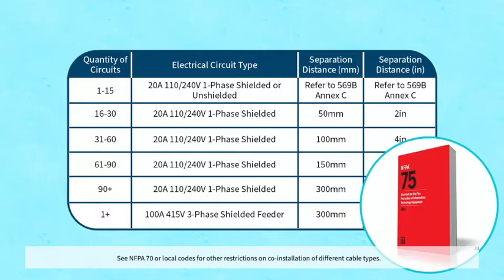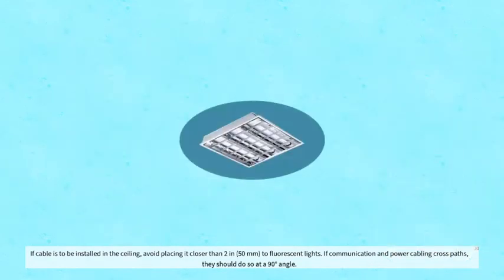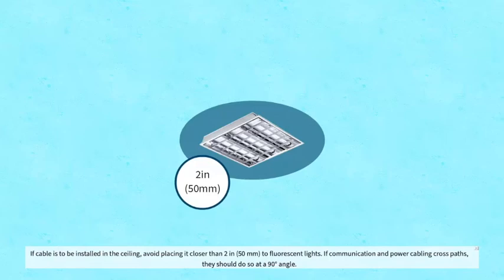See NFPA 70 or local codes for other restrictions on co-installation of different cable types. If cable is to be installed in the ceiling, avoid placing it closer than 2 inches or 50 millimeters to fluorescent lights. If communication and power cabling cross paths, they should do so at a 90 degree angle.